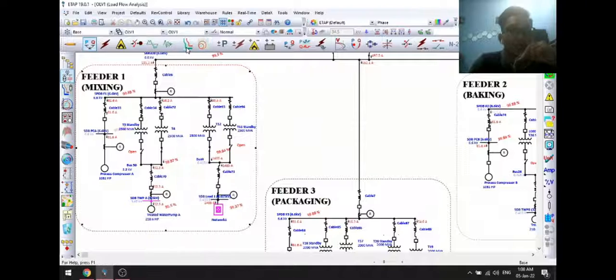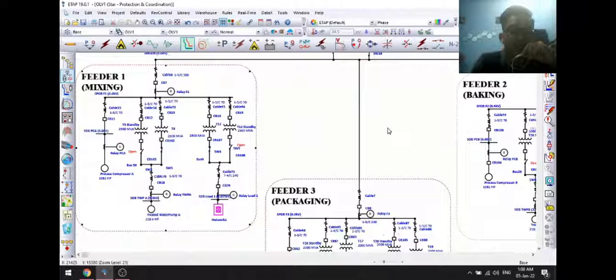Okay. Next, we go to the fault analysis. Fault analysis is divided into four: load, SPDB, SMGDB, and TMB. First we go to the load. If a fault occurs here, the circuit breaker will open here and here and here. So when a fault occurs at this load, all the systems in this area, feeder 2 and feeder 3, will still continue.